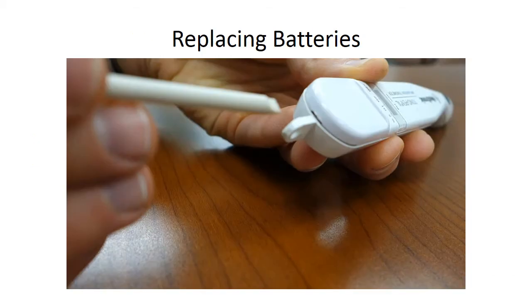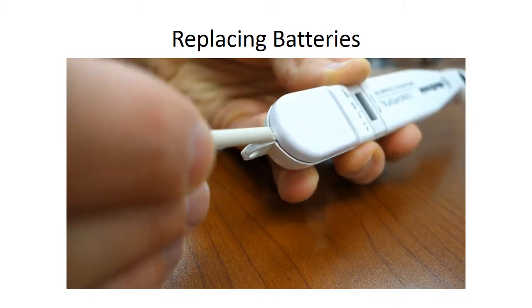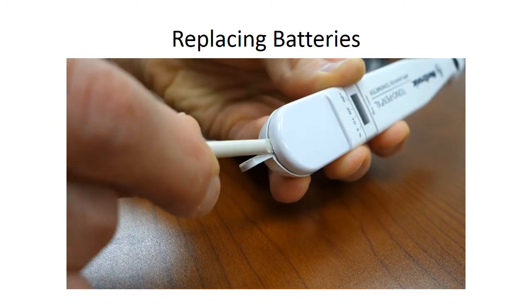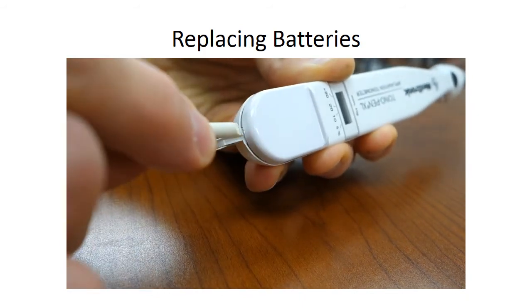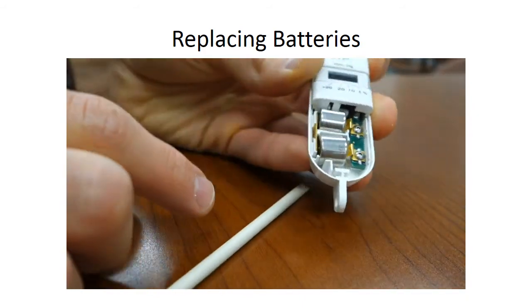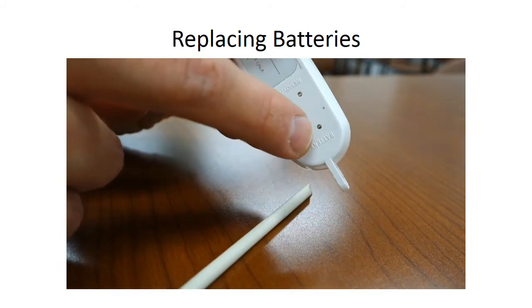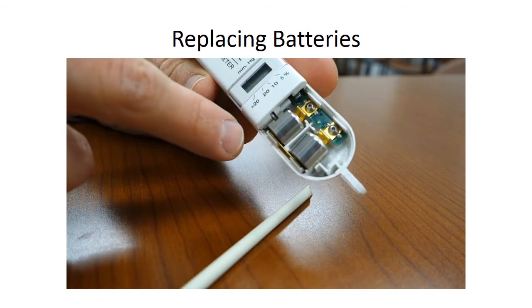The tono pen comes with a tool to open the device. Insert the tool into the back slot — there's a little hole there. Put the tool in and shimmy out the battery cover. You will have two batteries; to remove them, press on those two contacts and replace them with new batteries at the same time.